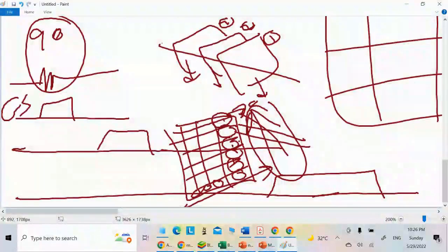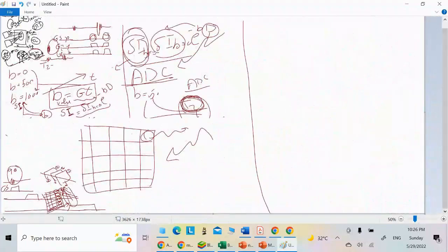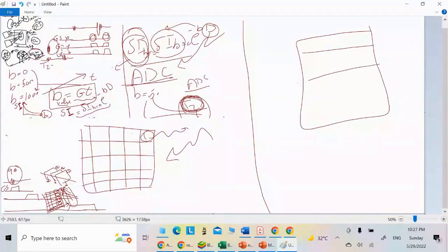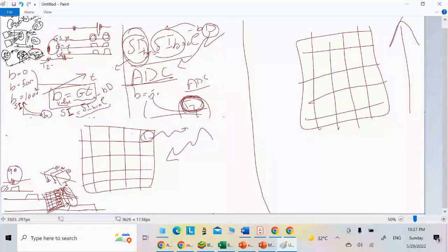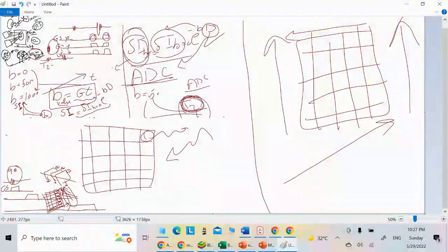The concept here is that now you have the gradient, which in reality is not only applied to this column, but also encompasses everything from the frequency encoding, which includes not just your entire section from bottom to top, but also all the voxels. So essentially, you have all the voxels that rotate during the recording process. And as you record them, they send you signals with different frequencies and different phases, which are crucial for the process. This allows you to perform differentiation and determine precisely where they are coming from any location and with what intensity. The intensity, in turn, depends on the level of magnetization.